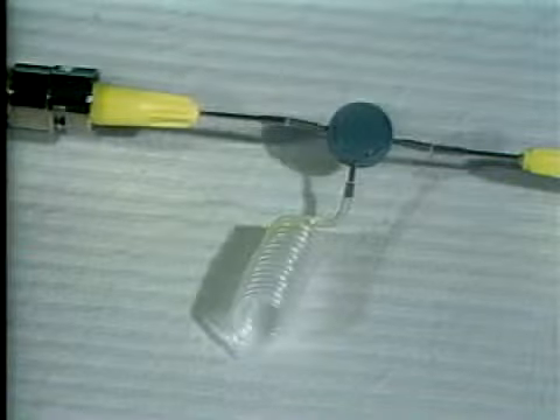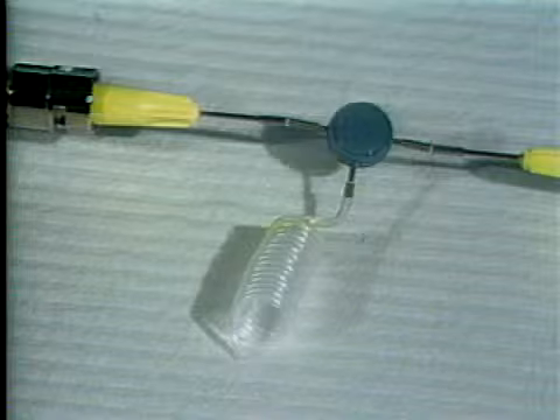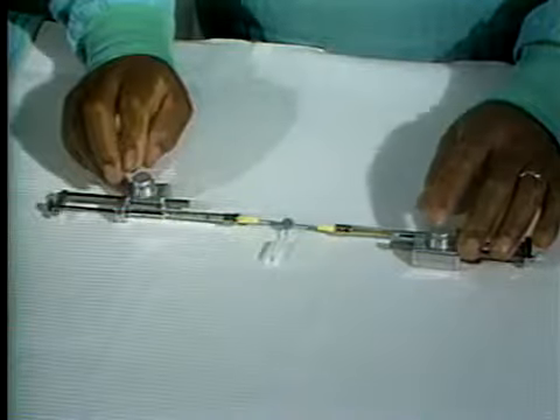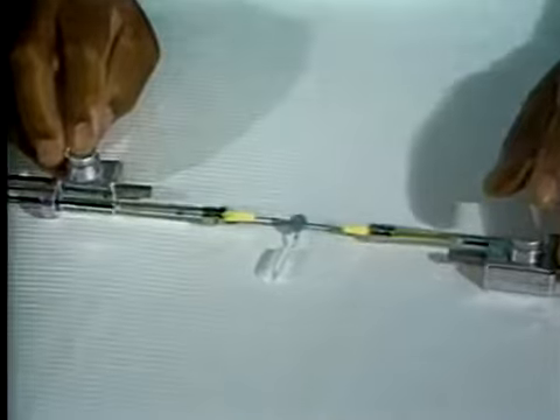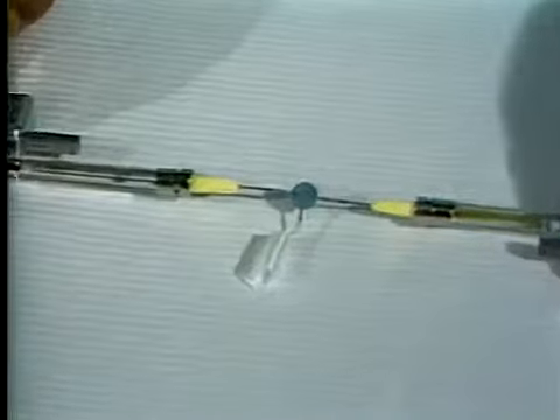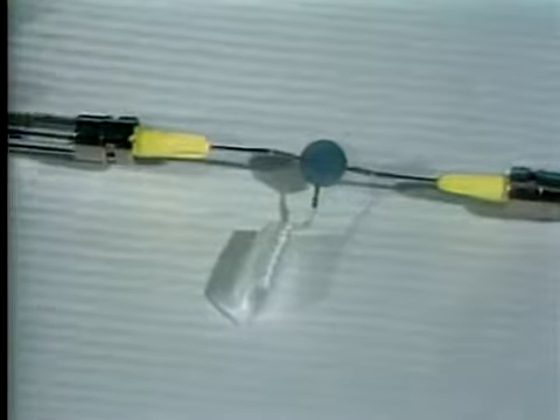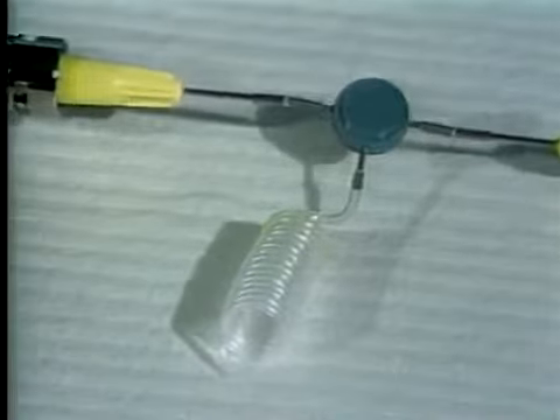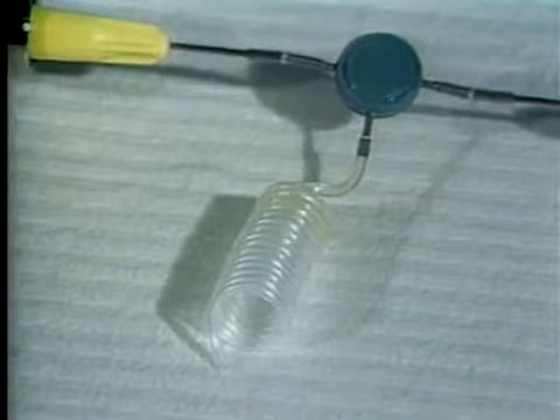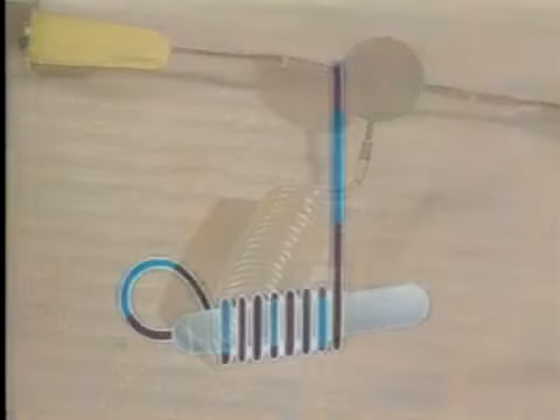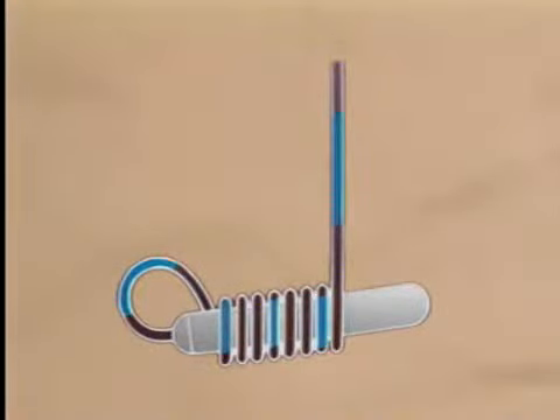To load the auxiliary reservoir coil, insert a Y adapter into the tubing and connect 2 microsyringes. Alternately load the coil with a solution from syringe A and a solution from syringe B. For demonstration purposes, mineral oil and air are being used here. When the filled coil is attached to the pump, its constant action will displace the fluid from the coil, resulting in an alternating series of infusions into the animal, or in controlled delivery of a drug solution incompatible with the pump interior.